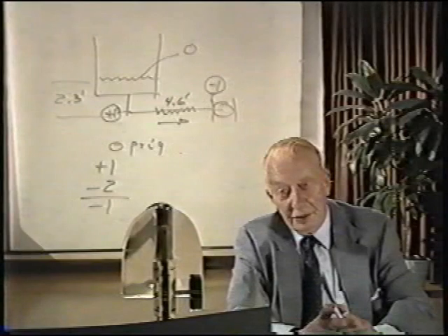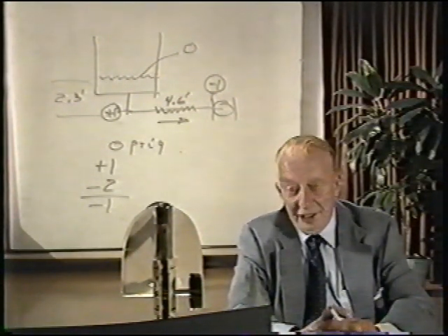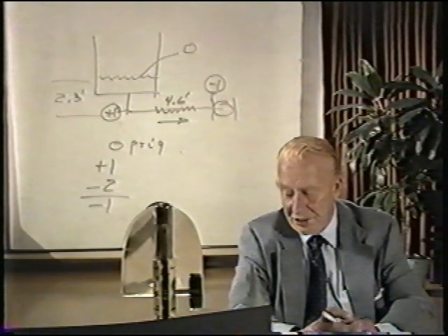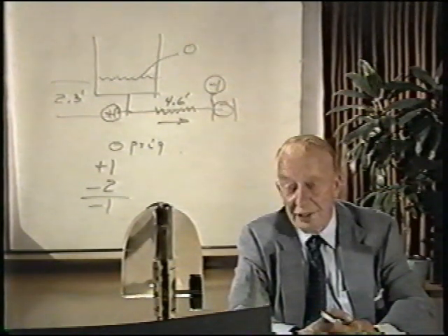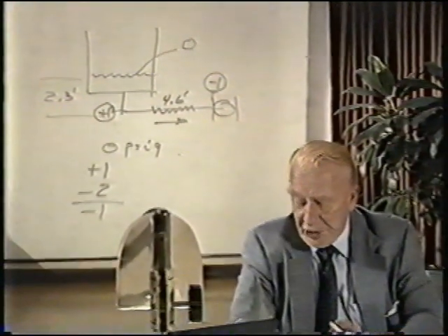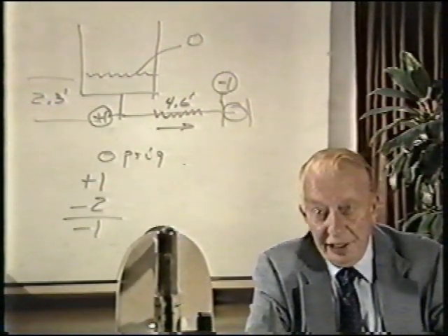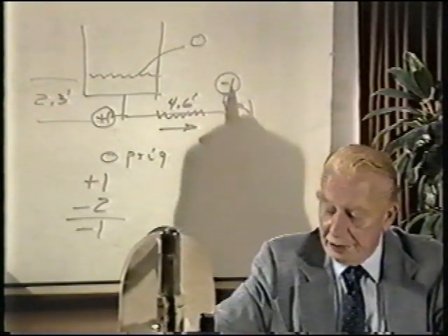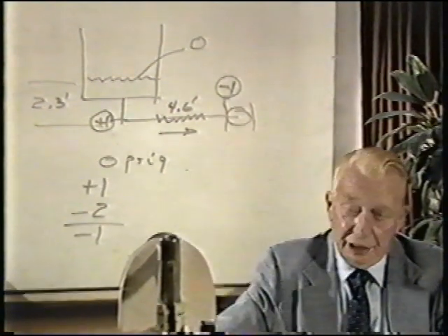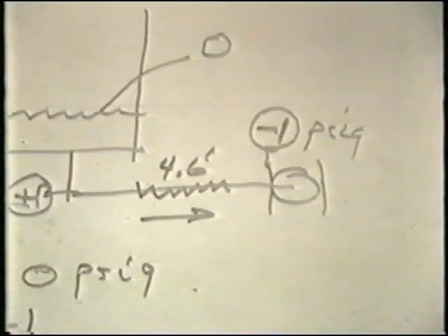But if we were to do so, we would mess up the whole situation. We would only take into account velocity head considerations when we're evaluating a pump system in actual operation. When we evaluate for the purpose of NPSH evaluation, we do not take into account velocity head changes. So we have then established a -1 psig as available at the pump suction flange.